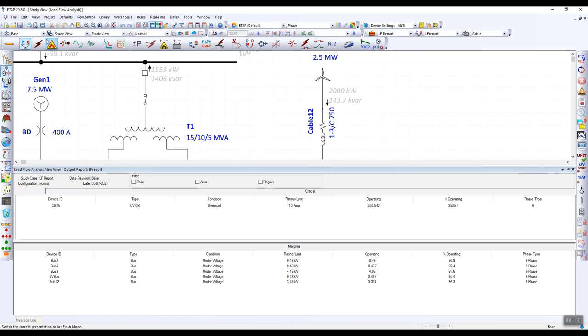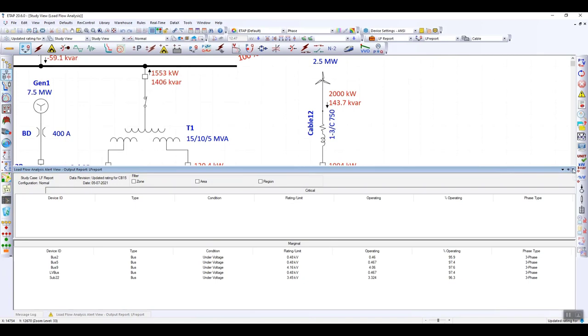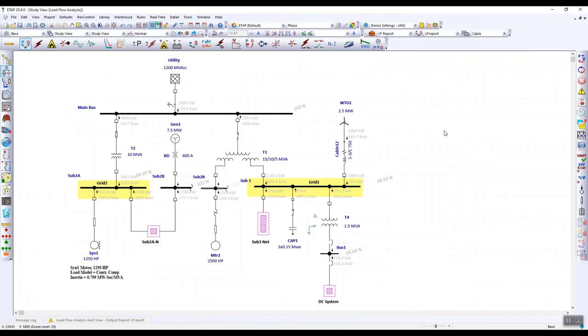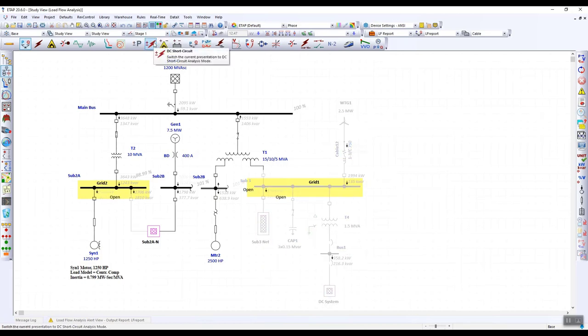We can then apply the new revision to the single line diagram and rerun our load flow calculation. So with this correction, it looks like circuit breaker 15 is no longer overloaded. We can also create scenarios where you can change the status for breakers, switches, and operating conditions for motors, utilities, and other loads. After applying the configuration, we see that there's a circuit breaker that's open since the right-hand side of our project is de-energized.